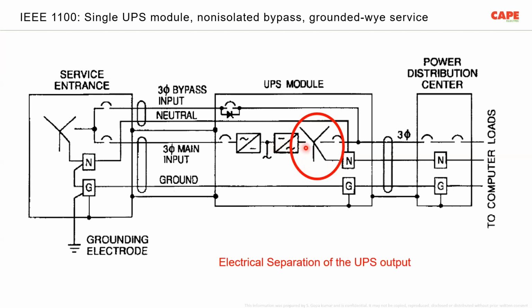The inverter output has an electrical separation. There is a star point, and the star point is the neutral. That means whenever the output computer loads are working from the inverter, this supply is an electrically isolated supply. It is an isolated supply from the transformer.